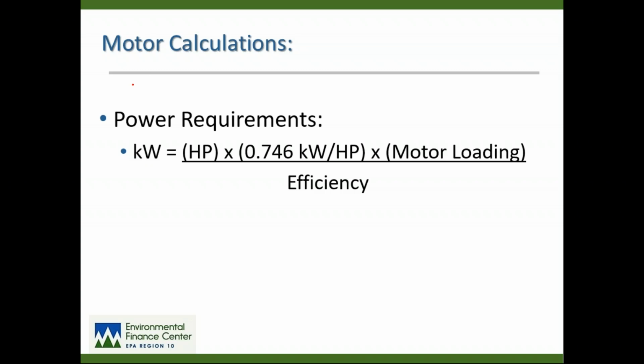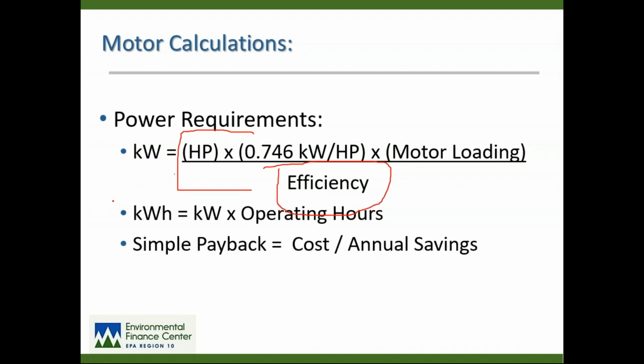So let's go through some real simple calculations when we're looking at motors. The kilowatts needed to drive a motor is a function of, and this is the equation, it's a simple equation, horsepower times 0.746 kilowatts times motor loading, and this is a decimal equivalent, divided by percent efficiency, and that's also a decimal equivalent, and I'll show you how that looks.